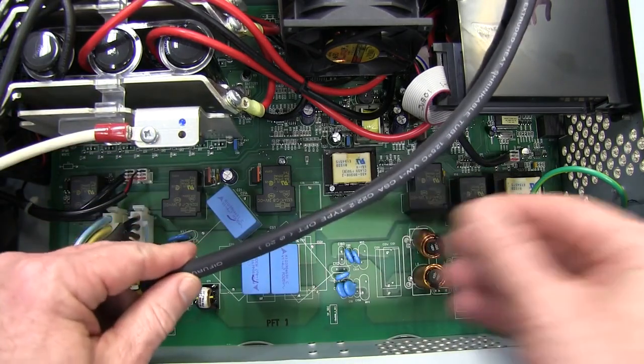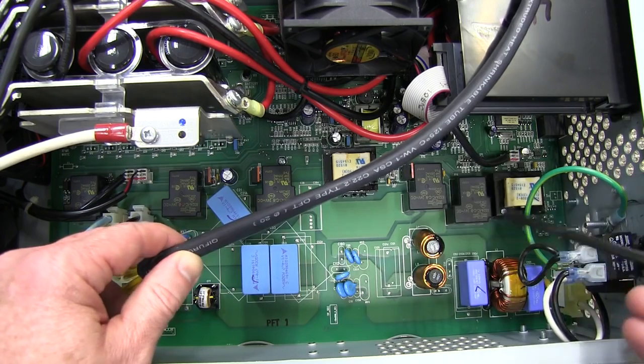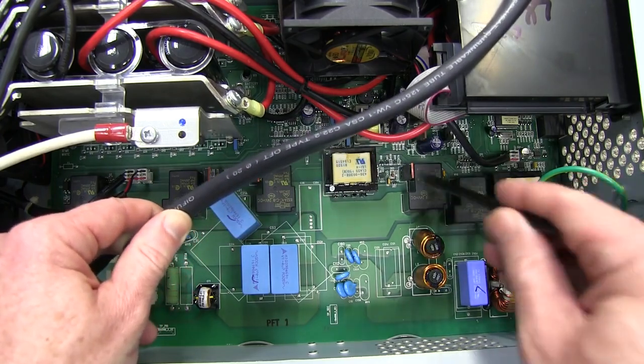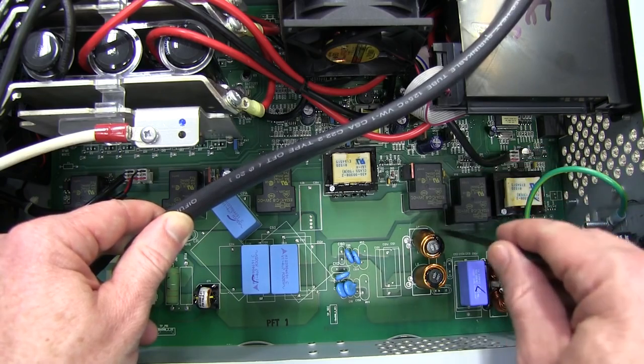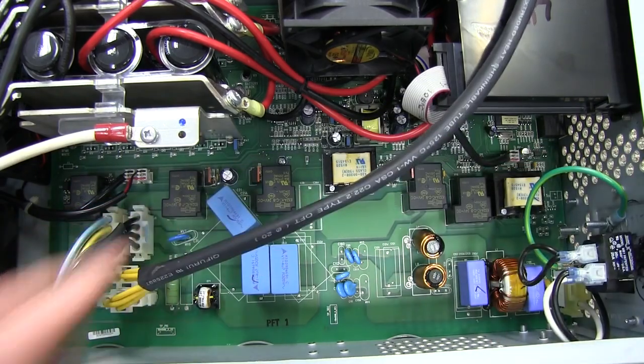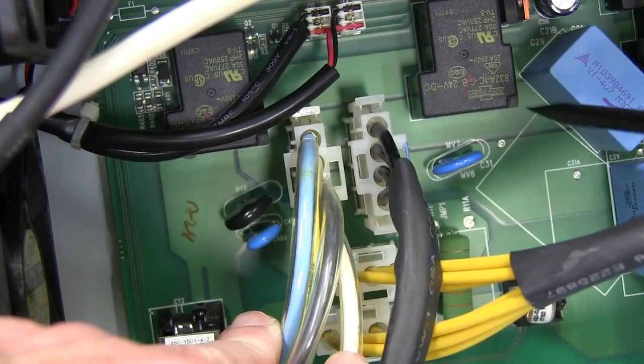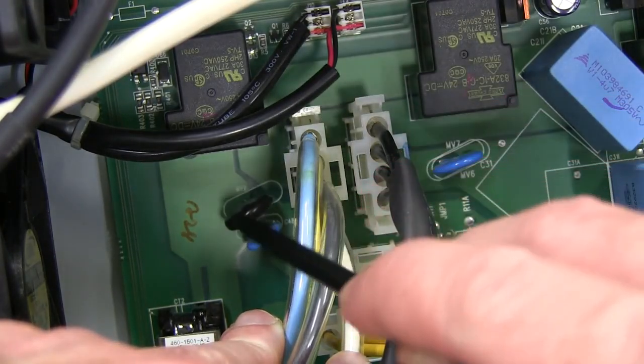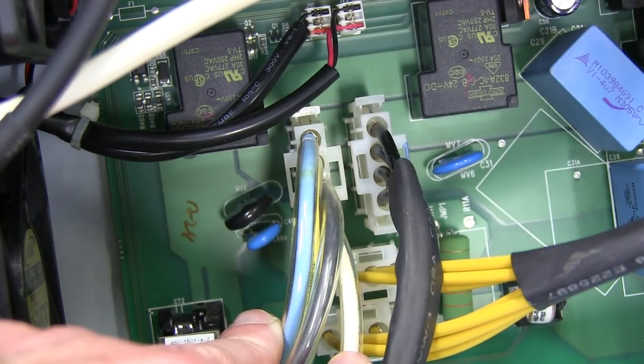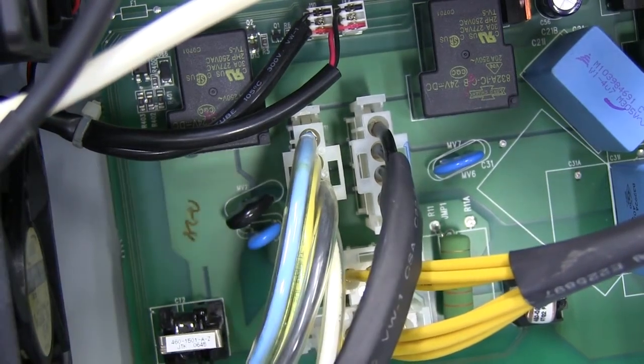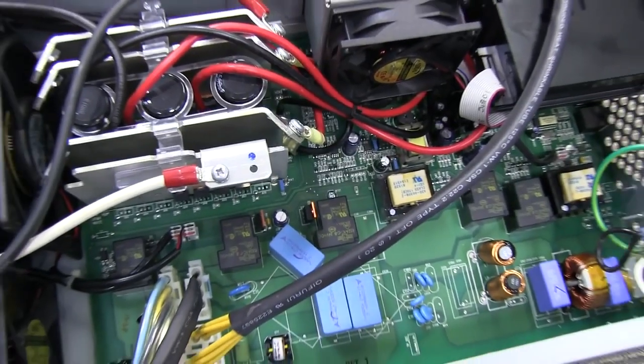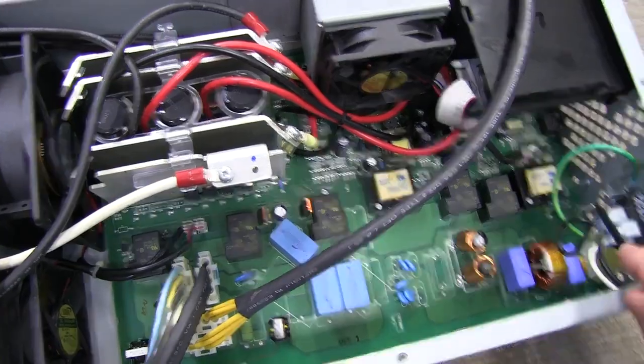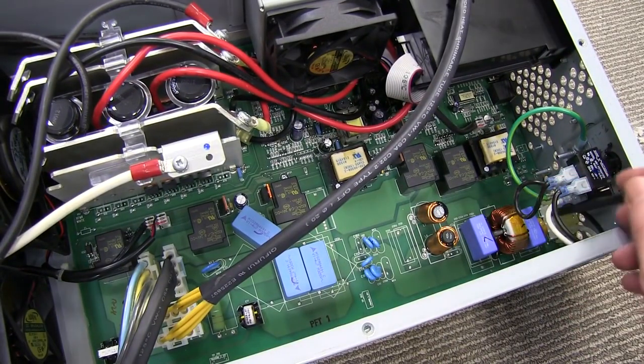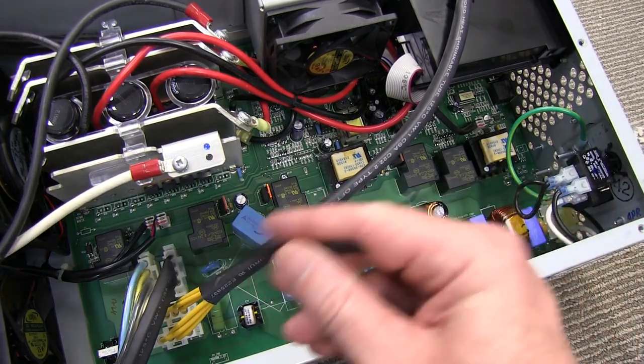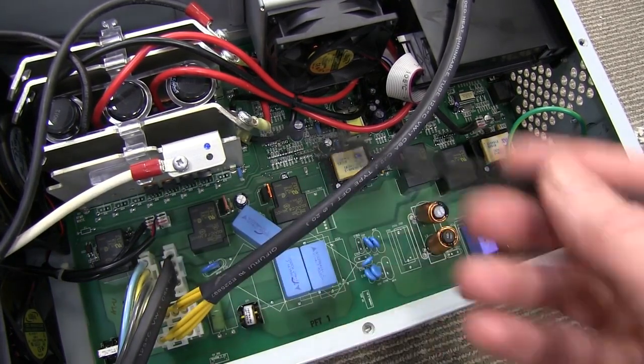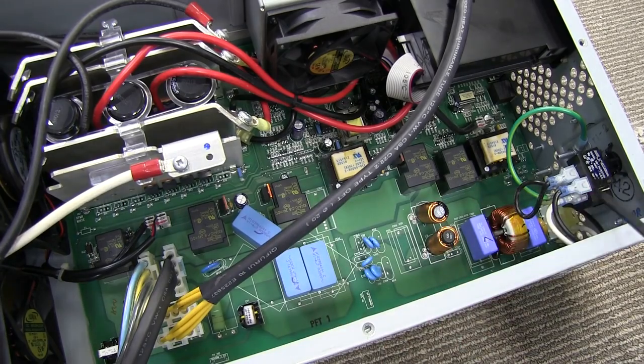I don't know the exact topology they're using for the auto transformer and the power bypass, but these ones also have beefy power tracks going through them. So make up your own mind, trace it out if you want to. We've got more protection here, another MOV there and another over there, so there's no shortage of protection in this thing, as you'd expect, because they claim it's part of the functionality of this UPS to basically clean up your input mains waveform. It filters it and clamps it with some MOVs, and the auto transformer configuration can slightly adjust and correct for the input voltage.